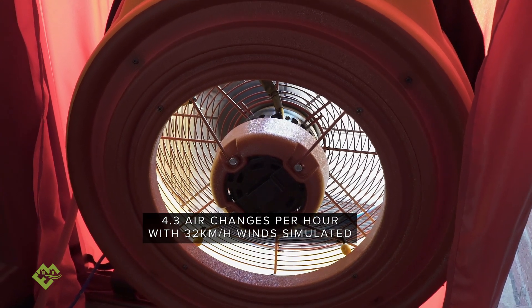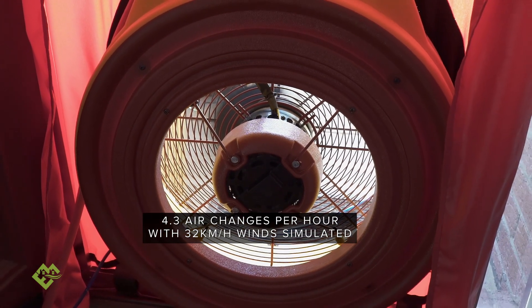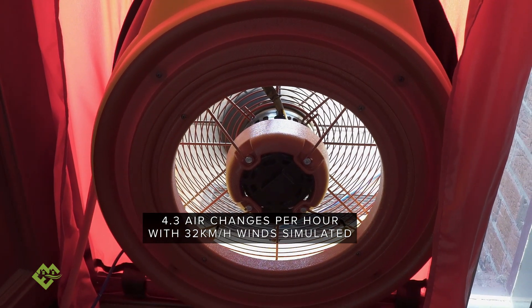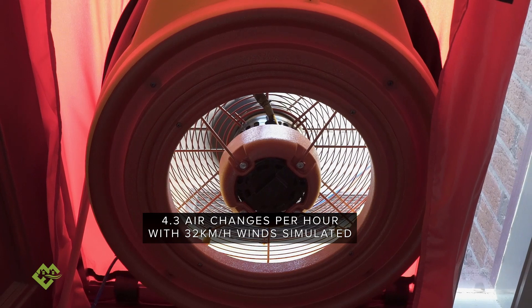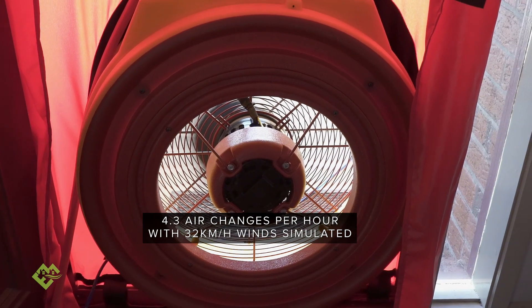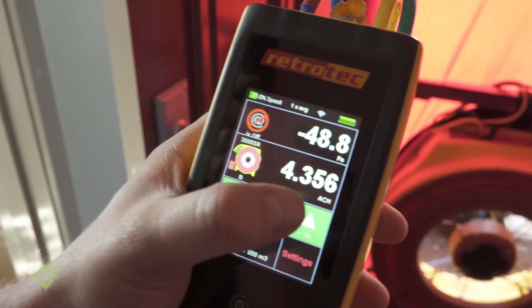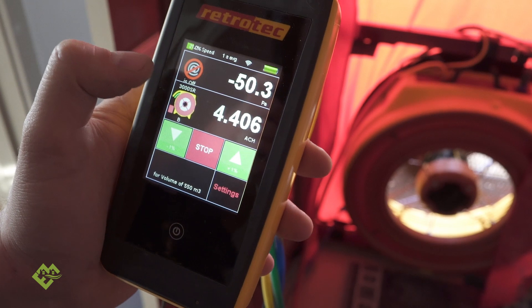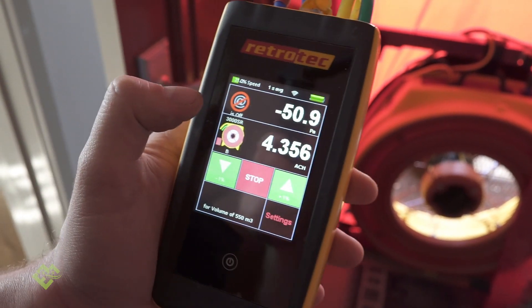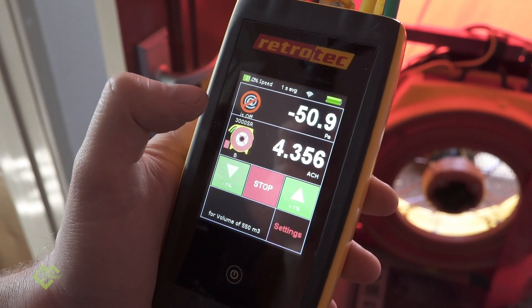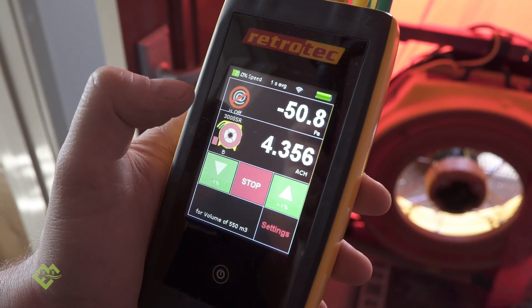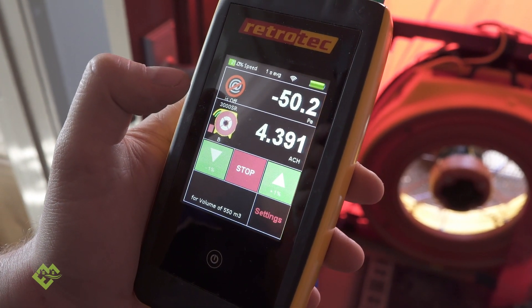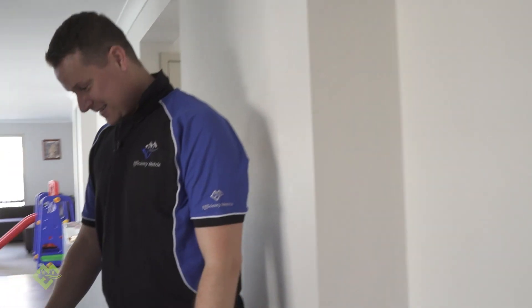4 ACH at 50 pascals — that's pretty good. Now that's with your ducted heating system sealed up. Should we do a quick check and take off the tape from the ducted heating system to see how it changes the number?